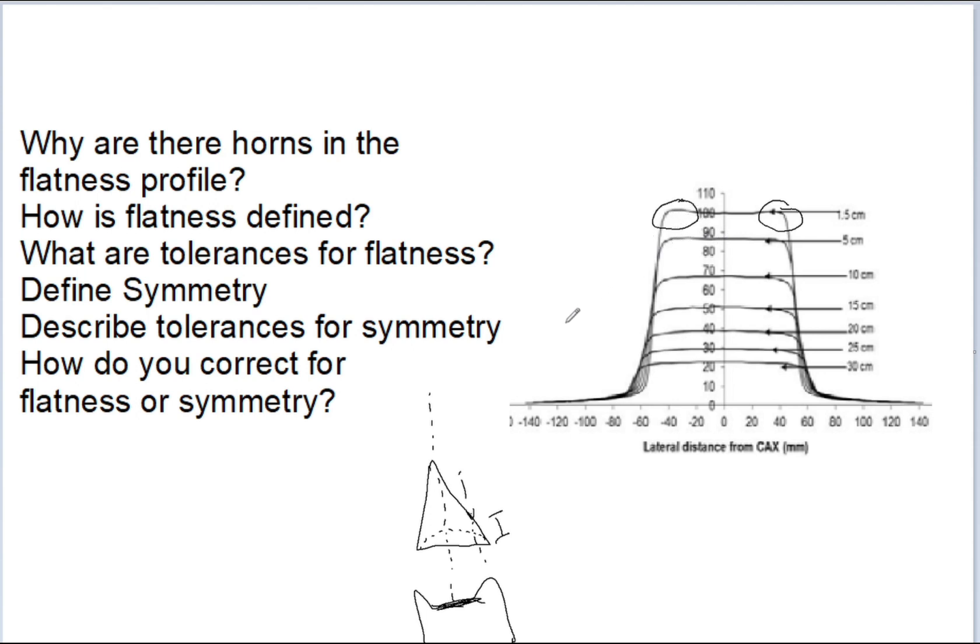Flatness is defined in actually a couple different ways. It depends on how your clinic defines it. Varian, Elekta, TG-45, all of these have their own different ways to define flatness. In my clinic, we use values inside the 80% field size and at a depth of 10.